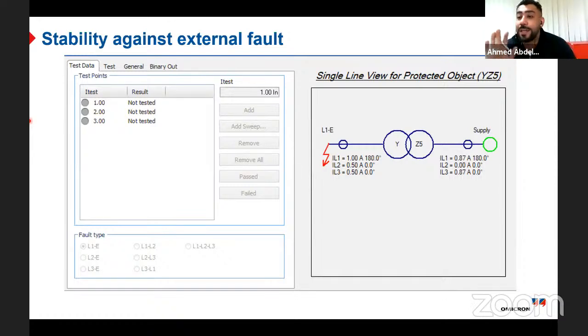Yes, it's a very good point. If you remember what we said, the generator itself doesn't have any influence on the differential protection, because the current in is equal to the current out. So we will consider it as a bar, as a conductor, nothing at all. I will take the CT before the generator at the neutral side, not on the terminal and not on the line side, and I will take the current of the CT for the transformer.